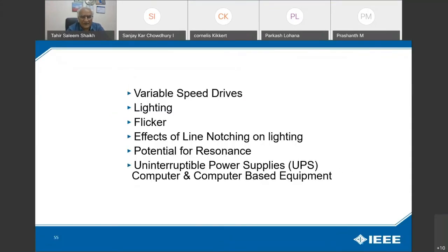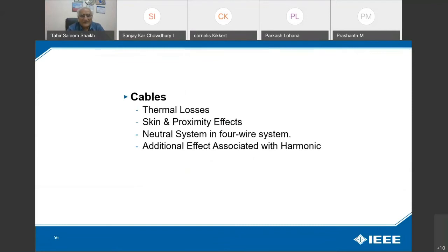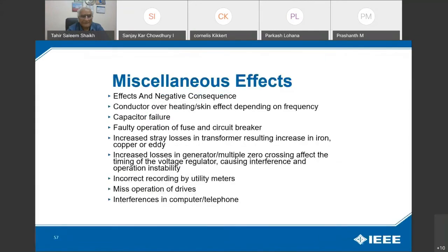There are so many other effects also: variable speed drives, lighting flicker, effects of line notching on lighting, potential for resonance, uninterrupted power supply, computer and computer-based equipment. Thermal losses, skin and proximity effects, neutral in a 4-wire system, additional effects associated with the harmonics, and negative consequences: conductor overheating, skin effect depending on frequency, capacitor failure, faulty operation of fuse and circuit breaker, increased stray losses in transformer resulting in increased iron, copper and eddy losses, increased losses in generator, multiple zero crossing effect, timing of the voltage regulator causing interference and operation instability, incorrect recording by utility meter, which is very important, misoperation of drives, and interference in computers and telephones.